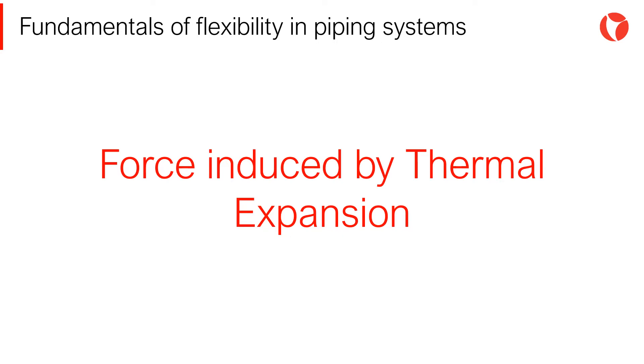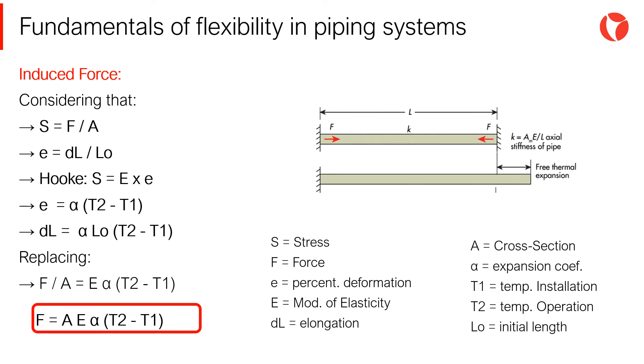When the system can freely expand at the ends of intermediate sections, this phenomenon does not represent any problem. However, when there are movement restrictions, stresses of considerable magnitude are induced in the piping system. As shown on the screen, it could be concluded that the force induced in the pipe depends fundamentally on its cross-sectional area and the difference in temperature.